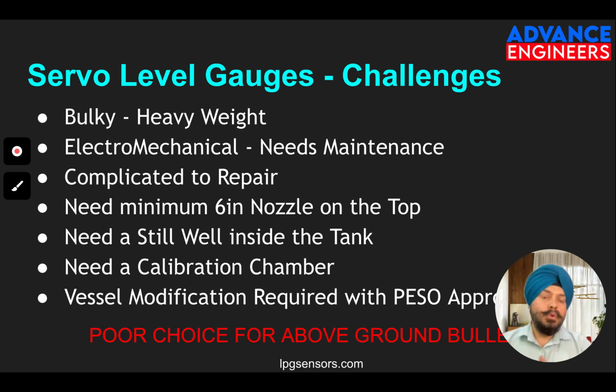So servo gauges are going to be a poor choice for above ground bullets, because these are small size bullets where the diameter is not more than 3.5 meters. They are already installed on a particular structure open to the atmosphere, where corrosion of the structure has already happened. They also have some structure on top for people to maintain and walk on. Now on that structure, you are also putting 1.5 tons of servo gauge and assembly, plus the still well.